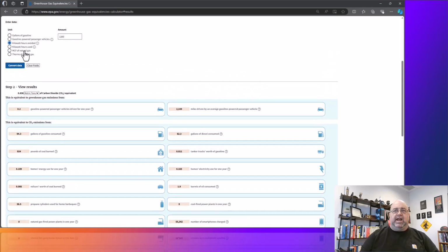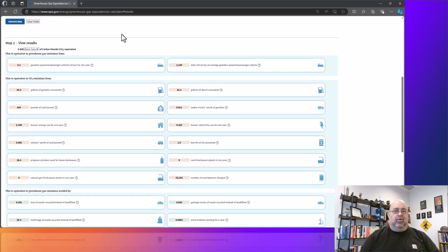That's in kilowatt hours, not megawatt hours. So that's 1.2 megawatt hours. That is greasing a bearing. Seriously. So you can reduce almost a metric ton just by greasing a bearing. Now, if you've got one motor in a plant, I can see where you say, well, maybe it's not worth it. But I saw one machine that was an older one, and they had just a dry bearing. It was 5 kilowatts. Now, it was a big motor. It was several thousand horsepower. And when we got done, it was massive improvements.